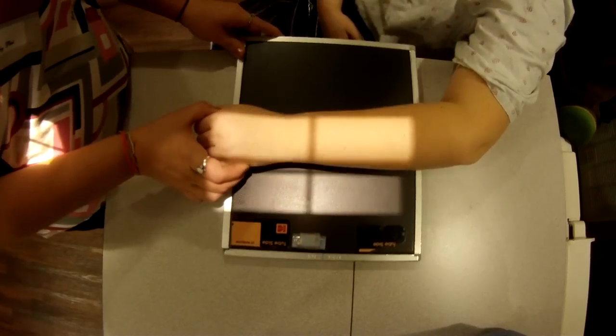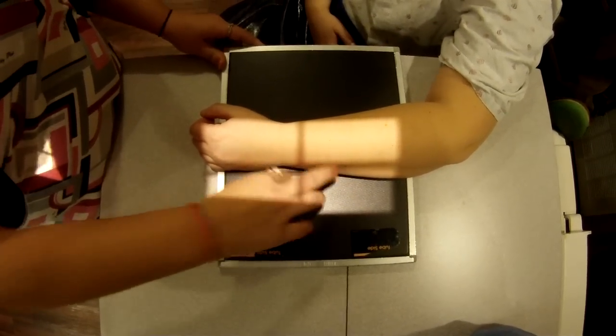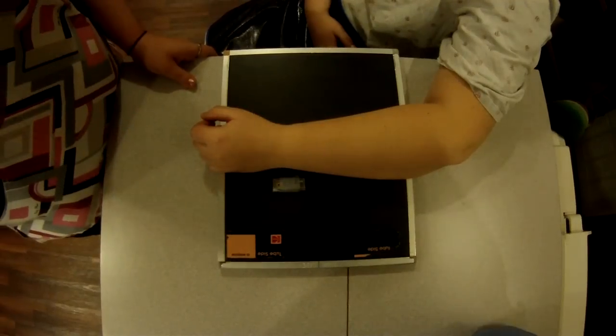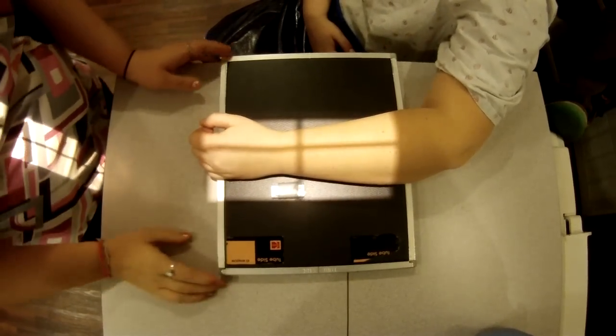Here's an example of omitting lead shielding on a multiple exposure film. This will result in unwanted density across the unshielded portion. The lack of shielding could also result in double exposure of the images.